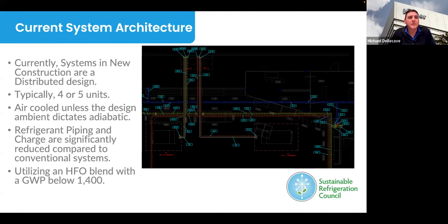Our current system architecture, which is what we've done for the last several years, is a distributed design. Our current standard store is 120,000 square feet. We have 4 or 5 distributed units utilizing an HFO blend currently with less than 1,400 GWP. Typically each unit is air cooled unless design conditions dictate something else, in which case it'd most likely be an adiabatic design. In addition to getting the compressors closer to the loads, we've implemented piping practices like loop piping that have decreased the overall charge of these systems.